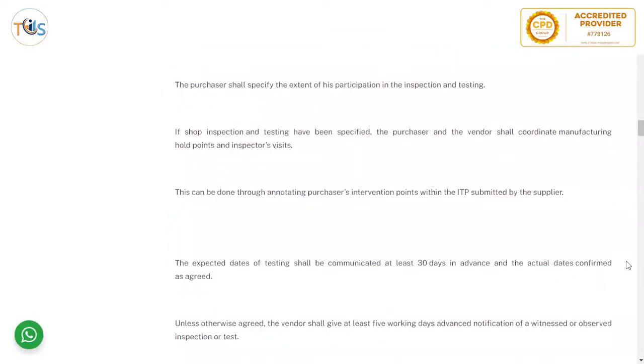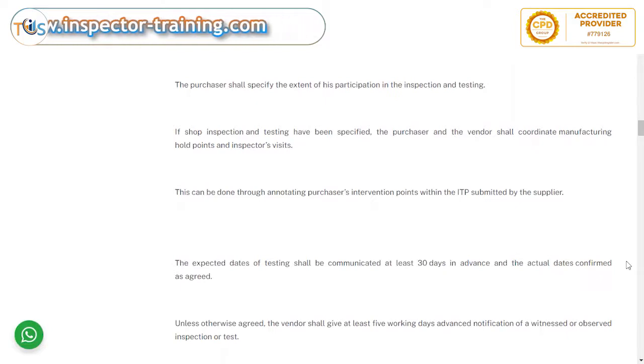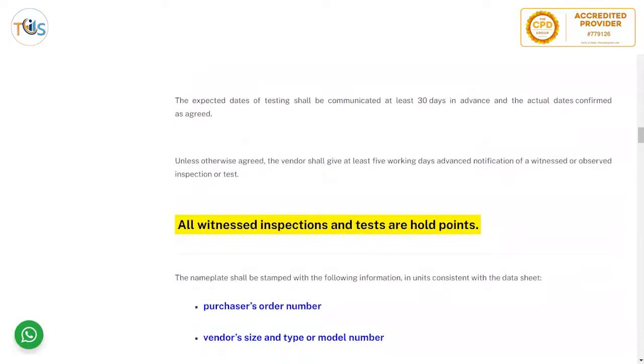The purchaser shall specify the extent of his participation in inspection and testing by annotating intervention points in the inspection and test plan. The purchaser and vendor shall coordinate manufacturing hold points and inspector visits. The expected dates of testing shall be communicated at least 30 days in advance, with actual dates confirmed as agreed. As the planned date approaches, the final notification per API is five working days in advance for a witness or observed inspection and test point.